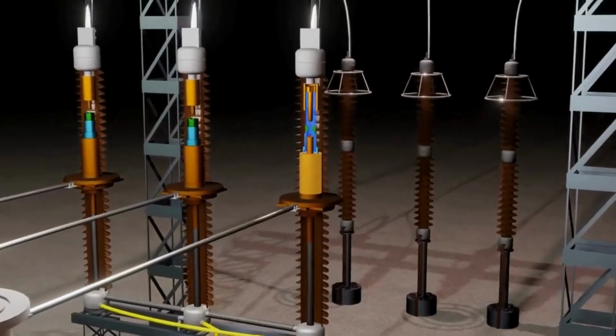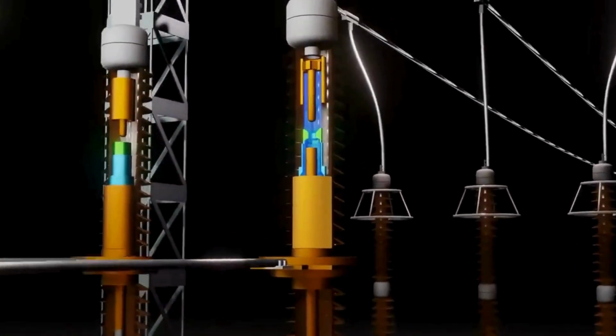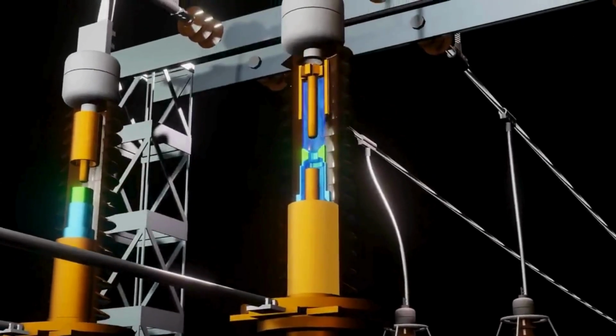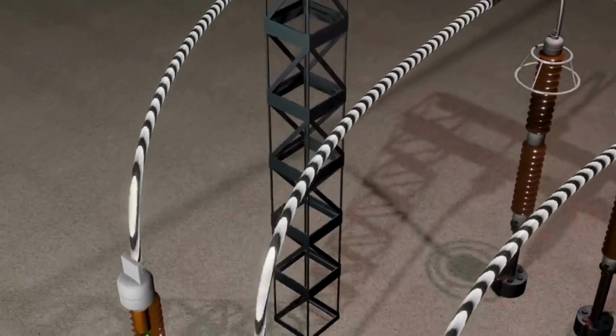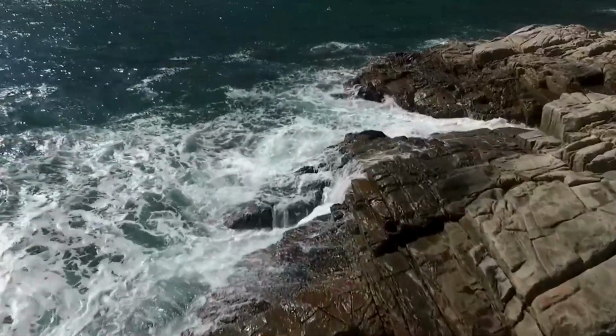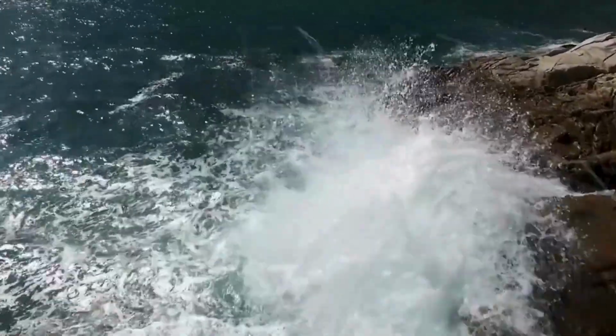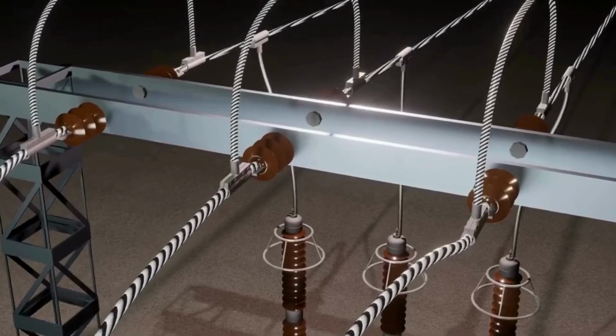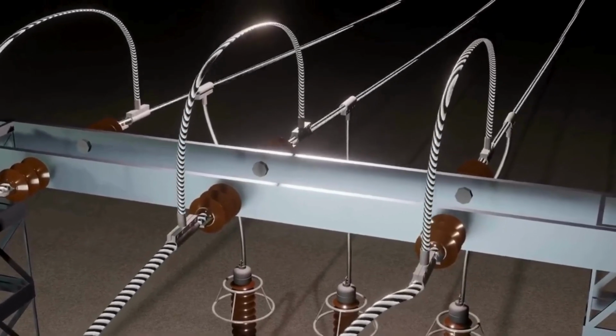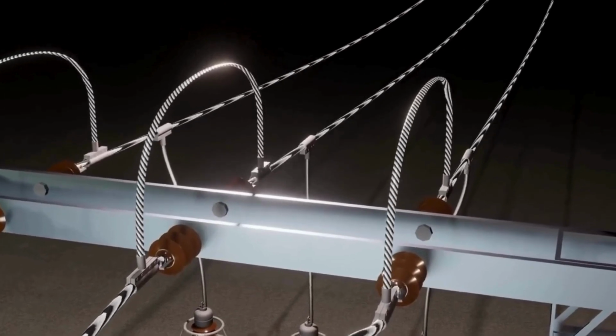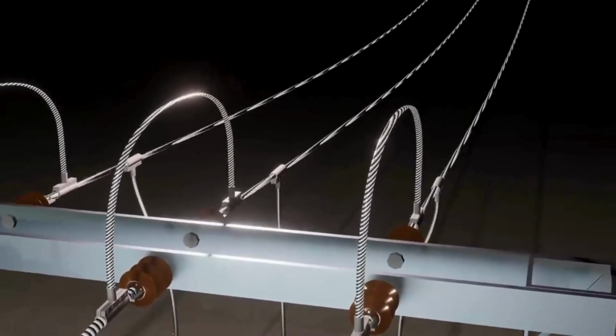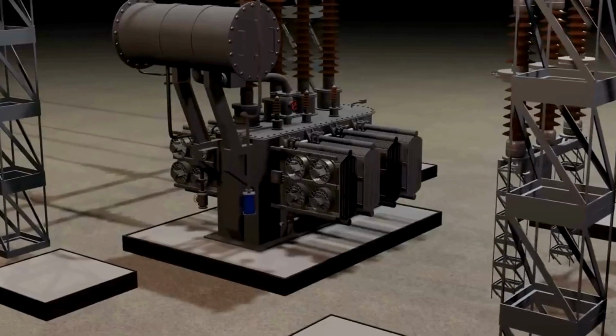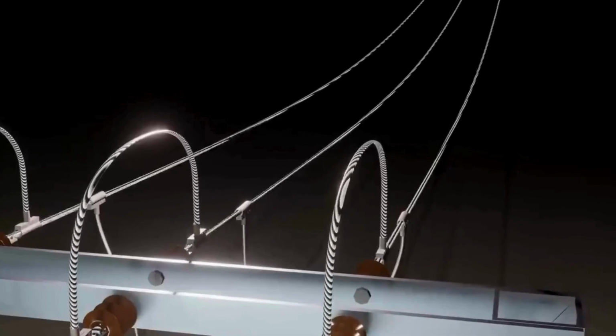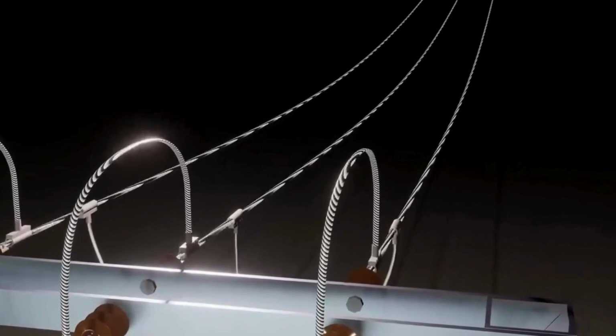Because the current that was flowing at high speed will not get any path to go, the current will reflect back from the contact of the circuit breaker. It is like when we stop water flowing at high speed, then waves start forming. This is exactly what happens with current, and this current is so powerful that the generator that generates electricity can become unstable or damage any transformer. Many devices are installed to keep the devices behind safe. So generally the power transmission line is not broken until there is an emergency condition or a forced fault.